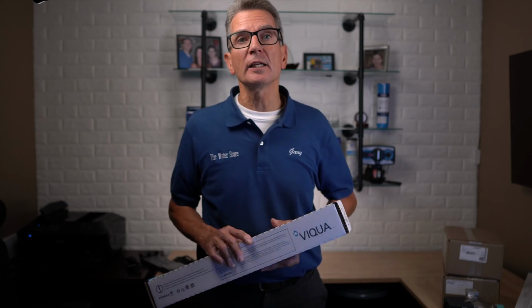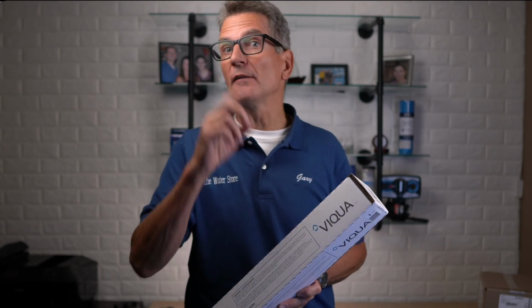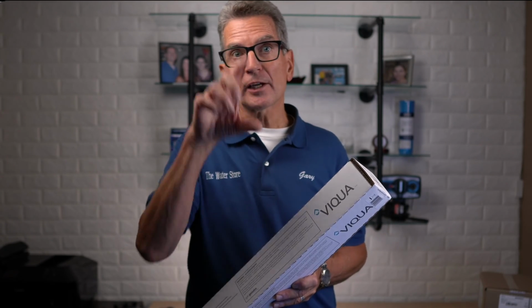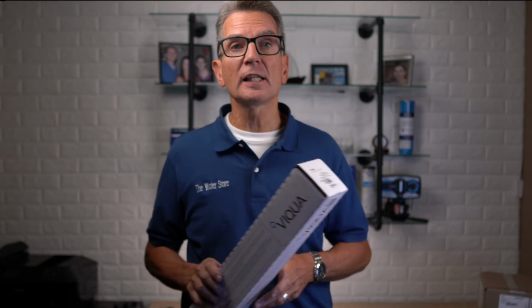Same thing goes with the sleeve. Now, one of the differences about the sleeve is that they are very fragile. The end is open, and it's very easily chipped and very easily cracked. And the other thing that's unique about these is that the sleeve goes in a certain way. So there's an actual arrow on the sleeve itself, but you can tell one end is tapered and the other end isn't, so you need to put it in the right way.